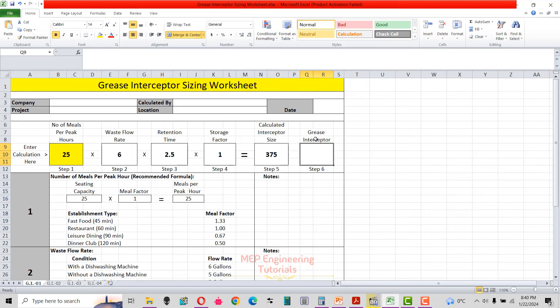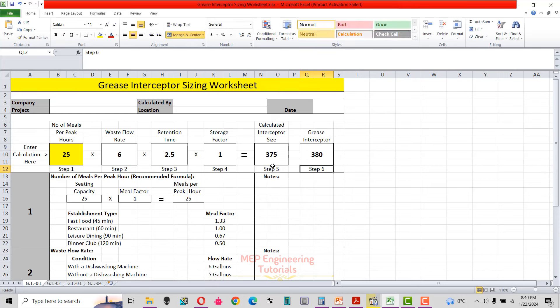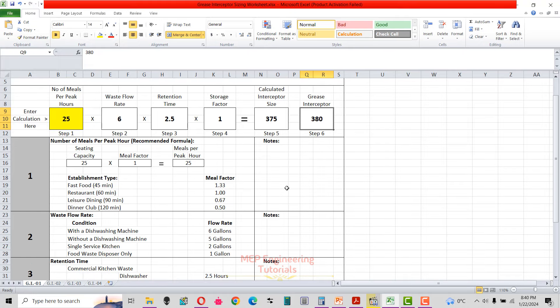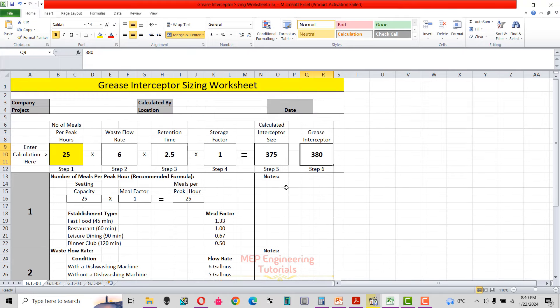Step 6: select the interceptor from the approved supplier's catalog to find the size closest to our calculated size of 375 gallons. After checking the supplier catalog, 380 gallons is the closest available size, so we select a grease interceptor of 380 gallons. This is how you calculate the grease interceptor size.